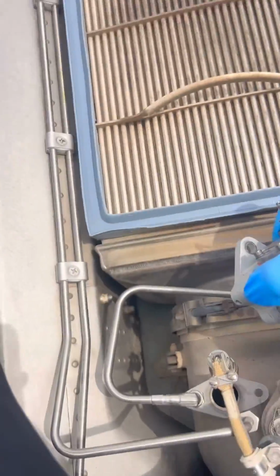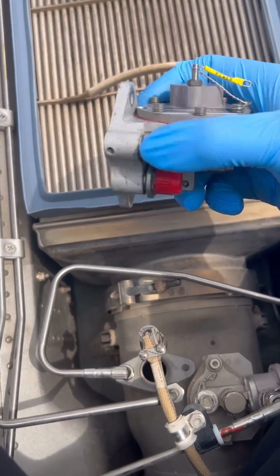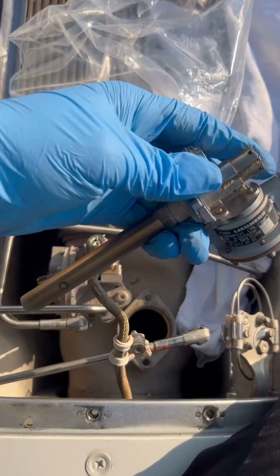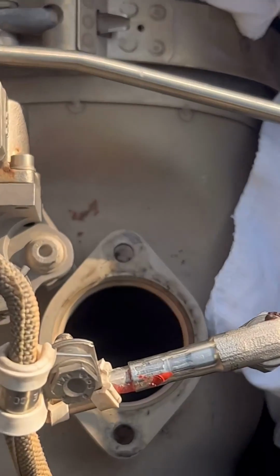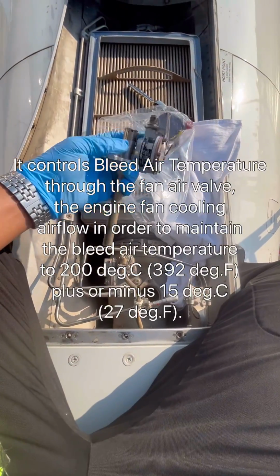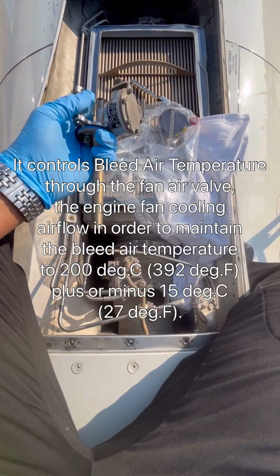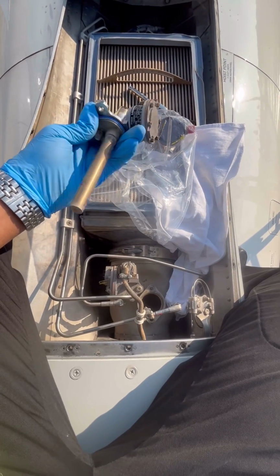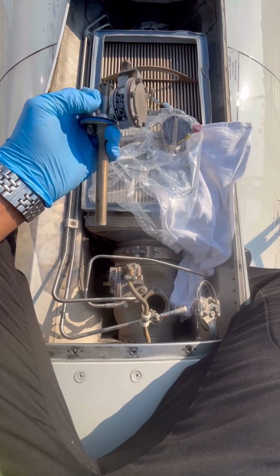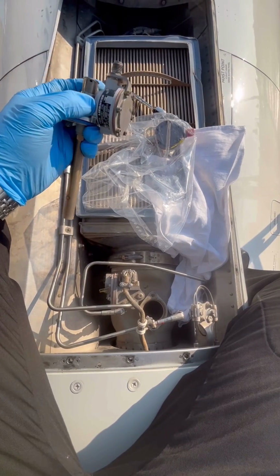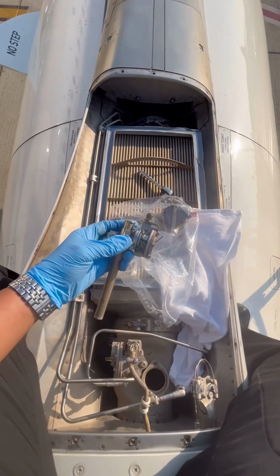Our next big component is our fan air valve control thermostat, located right next to our solenoid. This thermostat monitors the temperature of our bleed air and ensures it stays within specified limits. If it exceeds those limits, it sends commands to the fan air valve to open, increasing the cooling on our heat exchanger and reducing our bleed air temperature. This control is done via sense lines.